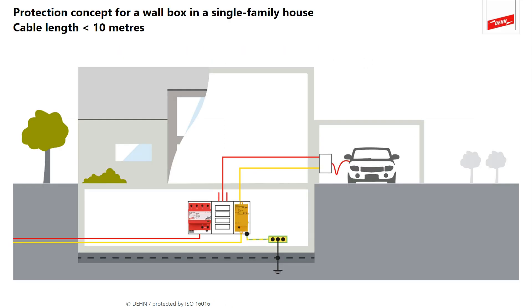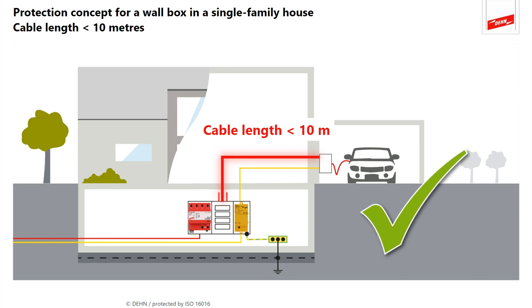Now back to the power distribution. The DEHNshield Basic combined arrestor not only protects the building installation but also the charging circuit for electric mobility. This means that both the charging post and the electric vehicle are protected during the charging process. The precondition is that the cable length between the main distribution board and the wall box is less than 10 meters. In this case the combined arrestor installed in the main distribution board is sufficient — no additional surge arrestors are required in the charging circuit.